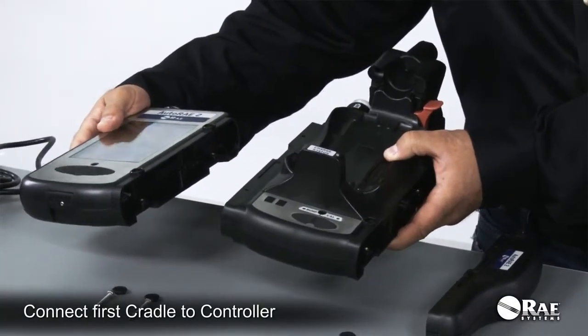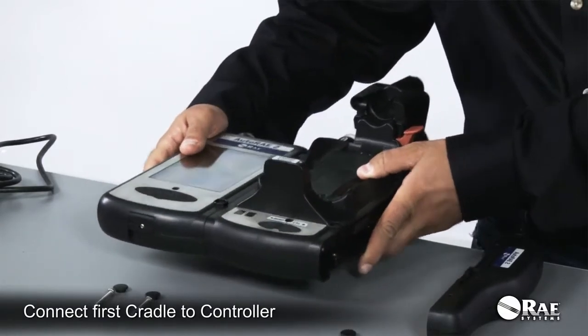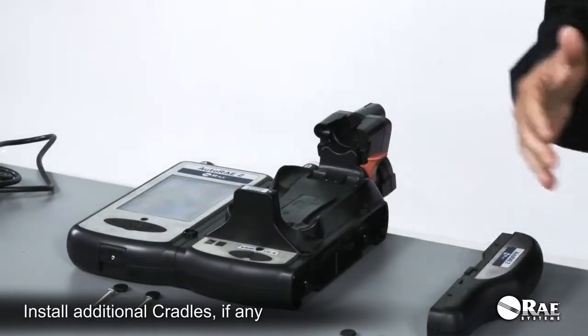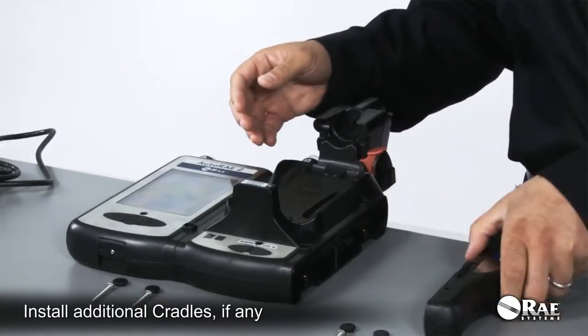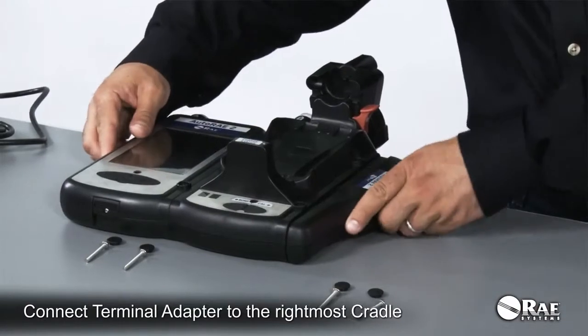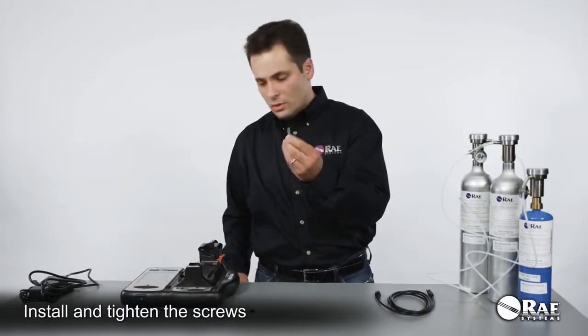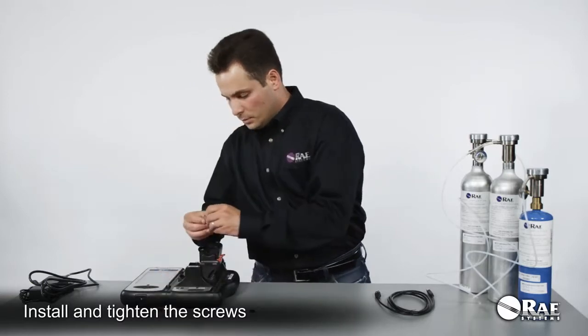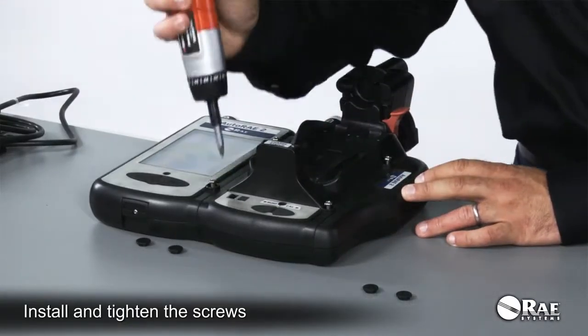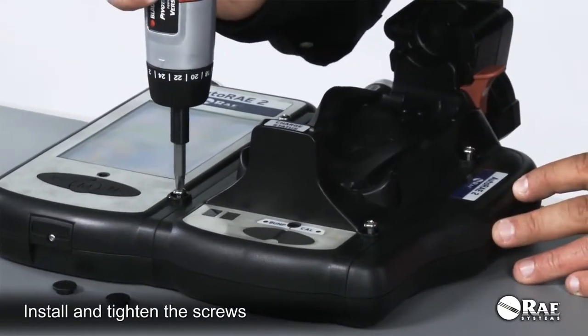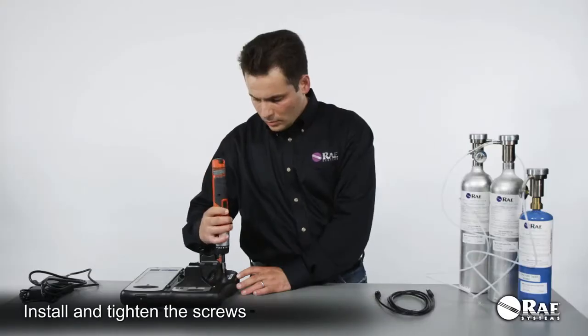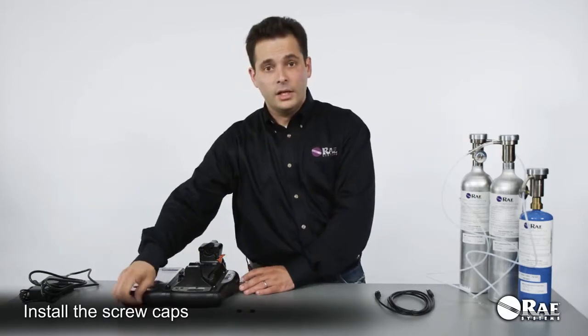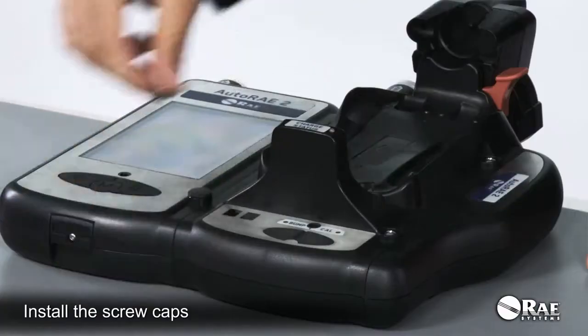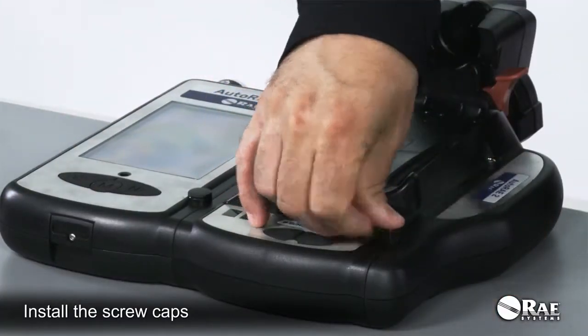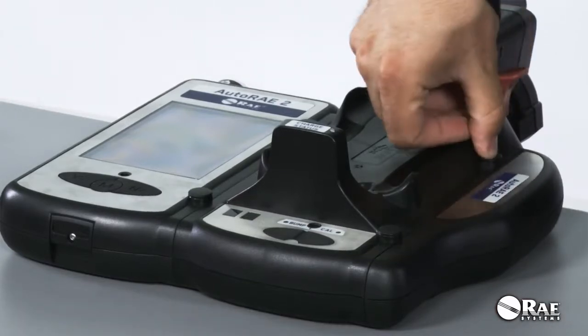Connect the first AutoRAE 2 cradle to the controller. Then if you have more cradles, then each cradle connects to the other one. And then at the very end goes the terminal adapter. Then use the screws to hold the system together. Tighten the screws. Next, install the screw caps. There are 4 of them. In this system, and then in systems with a larger number of cradles, you'll have more screws and more screw caps. The assembly process is now complete.